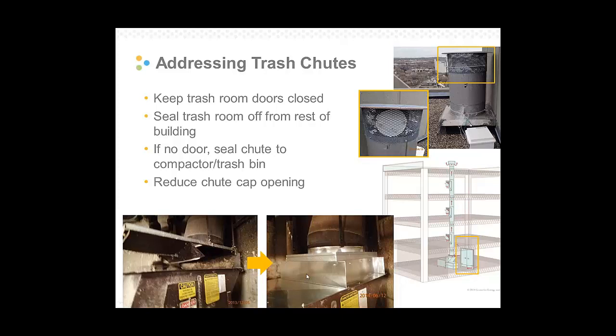Energy savings from these little modifications are difficult to quantify. We did quantify it on one. This is actually one retrofit we did on a singular chute. We did this modification where we lowered the cap and then did this dumpster room modification all in the same building, and they saw about $1,500 per year in annual energy savings. But we had to do some long-term data logging in order to get an estimation of what their savings were. It's very weather dependent, so hard to quantify.